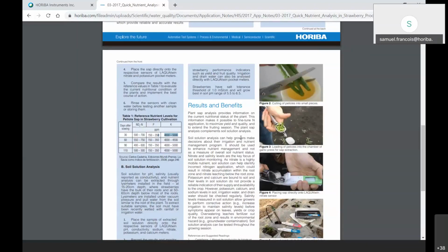So our calcium meter is measuring the free calcium. In comparison with a laboratory testing, a lab testing will be measuring the total calcium, where we are measuring the free calcium. So normally, our calcium measurement is lower than the lab. So it's strange that you get a higher reading than in the lab. If it's possible, I would like you to send me the data and look at it to understand a little bit better.